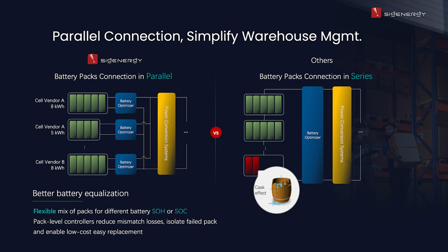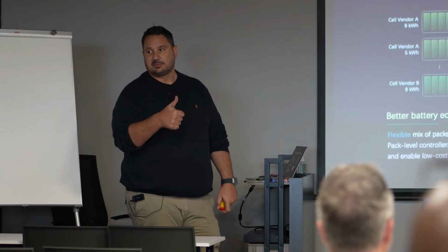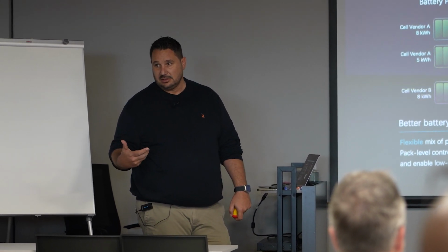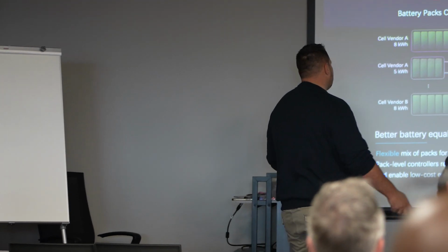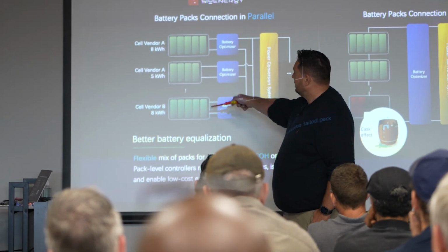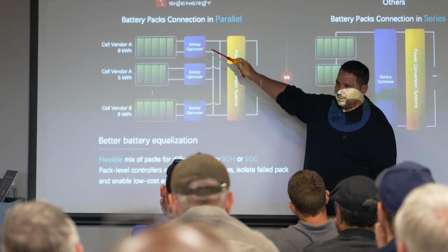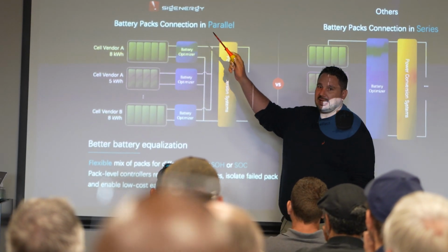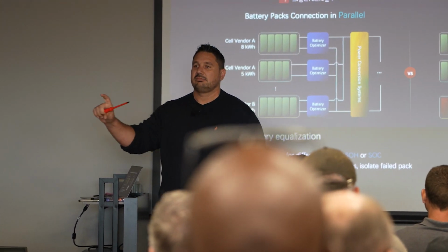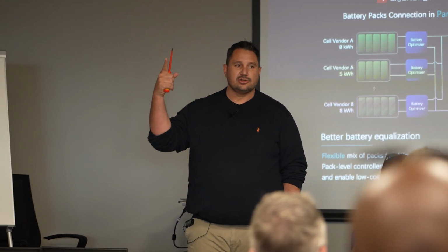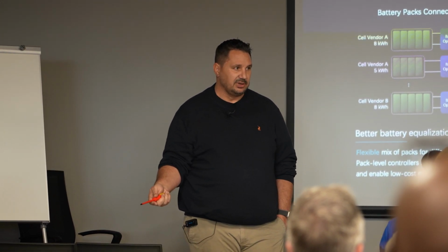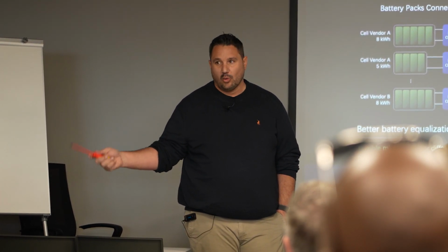So each one of these batteries has got a battery optimizer in them. So what it does is it takes the 32.85 volts, boosts it all the way up to 600 for the inverter to accept. So when you have a battery that's dead over here, those two can still keep your system running. So anytime you lose a battery on the system, it stays on. It just red lights that battery, sends you a notification, tells you that that battery needs to be replaced. The system does not go off.